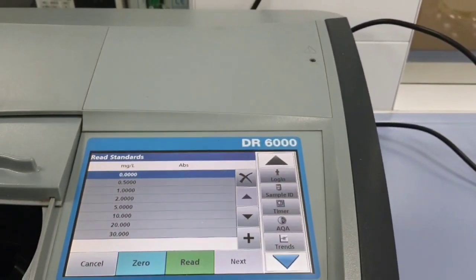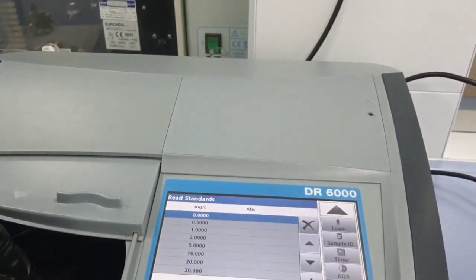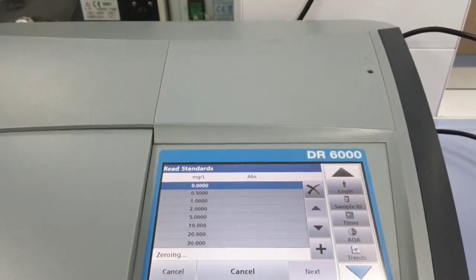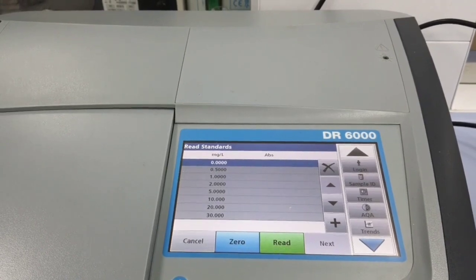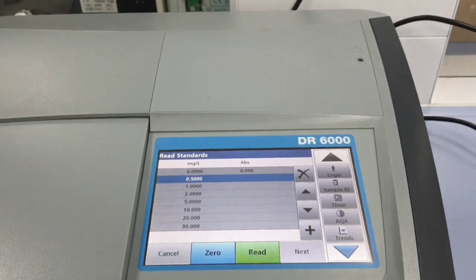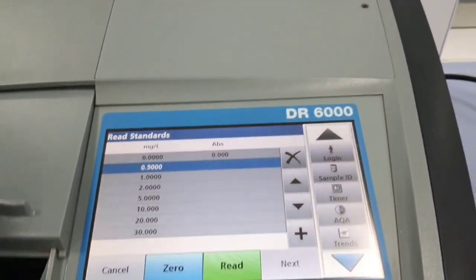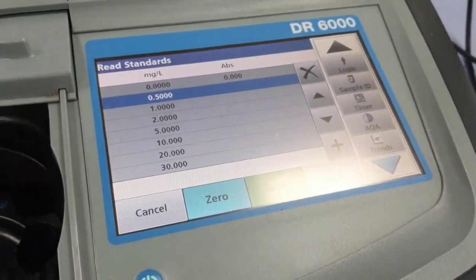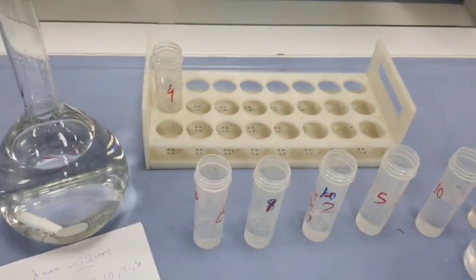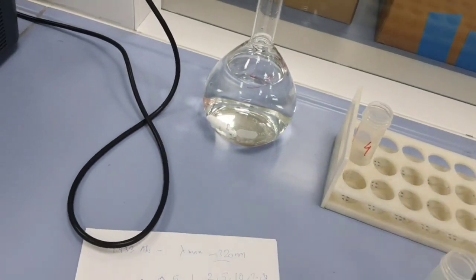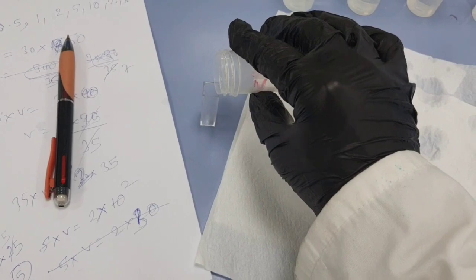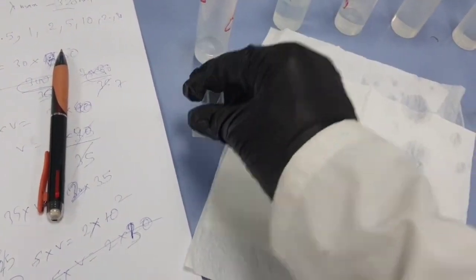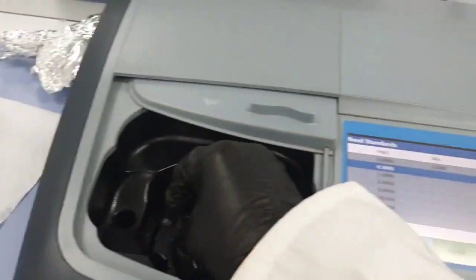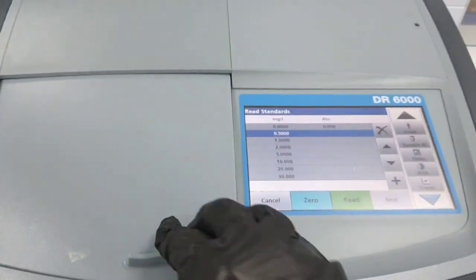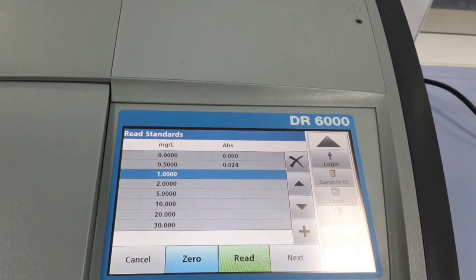First we have to zero it. For zeroing, we have added deionized water, and I'm going to press 0. It's already 0, so I'll say read. Now I have to add 0.5 ppm of ciprofloxacin, which I have already prepared. I'll transfer it here. Make sure there is no thumbprint and no dirt on the cuvette. This is our quartz cuvette; I already discussed why we use a quartz cuvette and not a glass one. I'll press read. The absorbance is around 0.024.